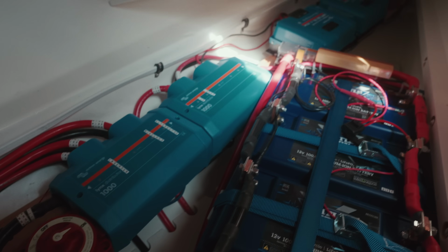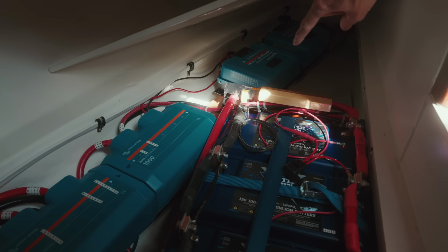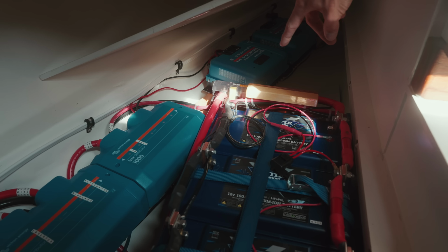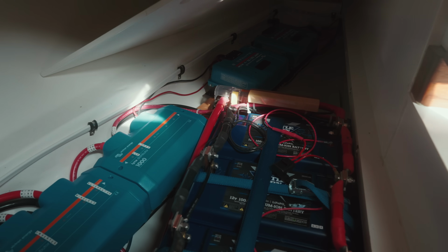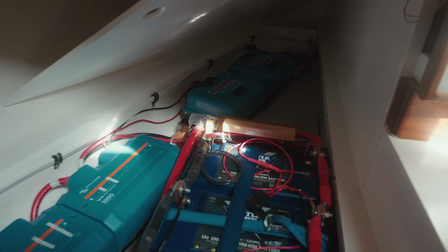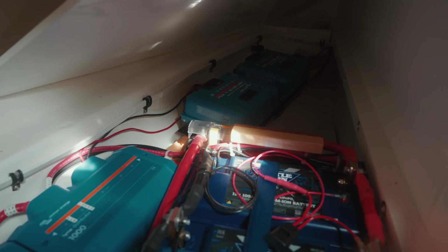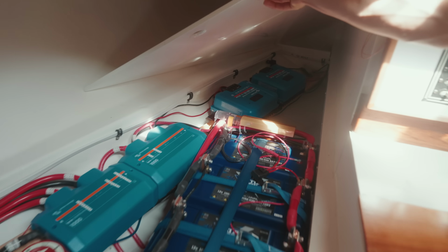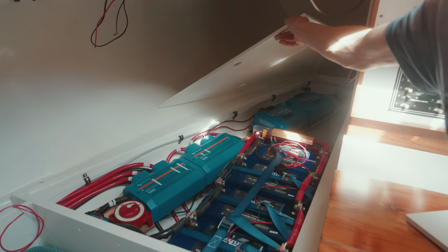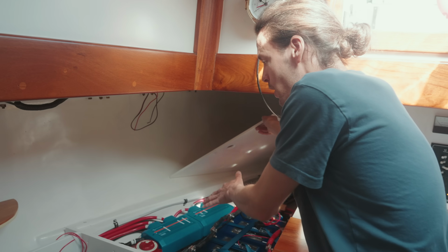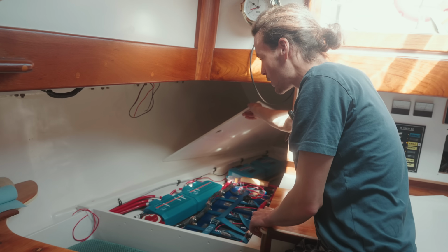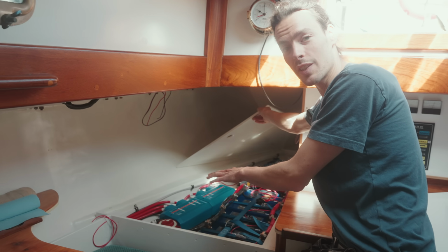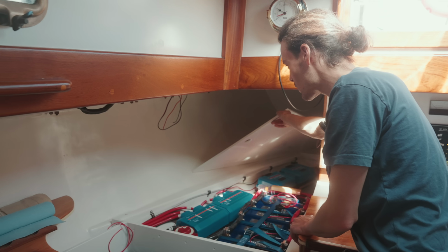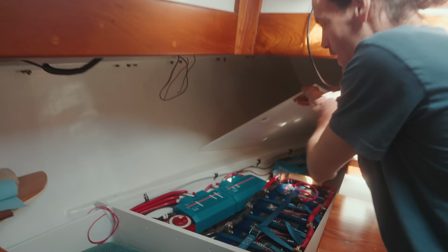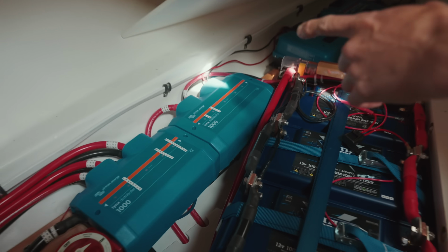Back there, that's a T-class 400 amp fuse, as close to the terminal as possible. Then we wanted to feed positive one way, negative the opposite way. That's just the proper way of doing it, I've heard. Then all the loads go to all the places. I even managed to put in a little labeling, so I know that one there is feeding the load panel, the DC panel.